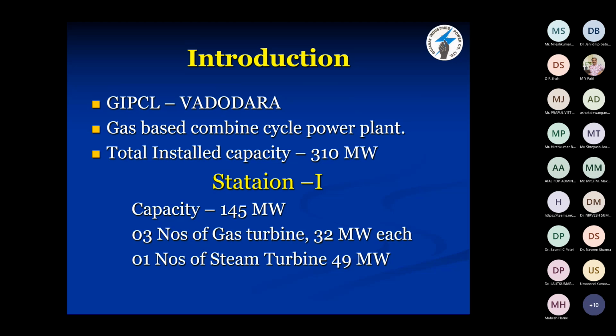Now GIPCL at Vadodara, because I am here in the Vadodara plant, is a gas-based combined cycle power plant, with a total installed capacity of 310 megawatt. Now our Baroda plant has two stations. It is divided into station 1 and station 2, because in my presentation I will use the words station 1 and station 2, so you will not be confused. Station 1 has 145 megawatt, and it consists of 3 gas turbines of 32 megawatt each. That is a BHEL frame 6 gas turbine machine. All 3 gas turbines have individual HRSGs, that is heat recovery steam generators, and the common steam goes to the steam turbine, and it has one steam turbine of 49 megawatt capacity. So this is the configuration of station 1.